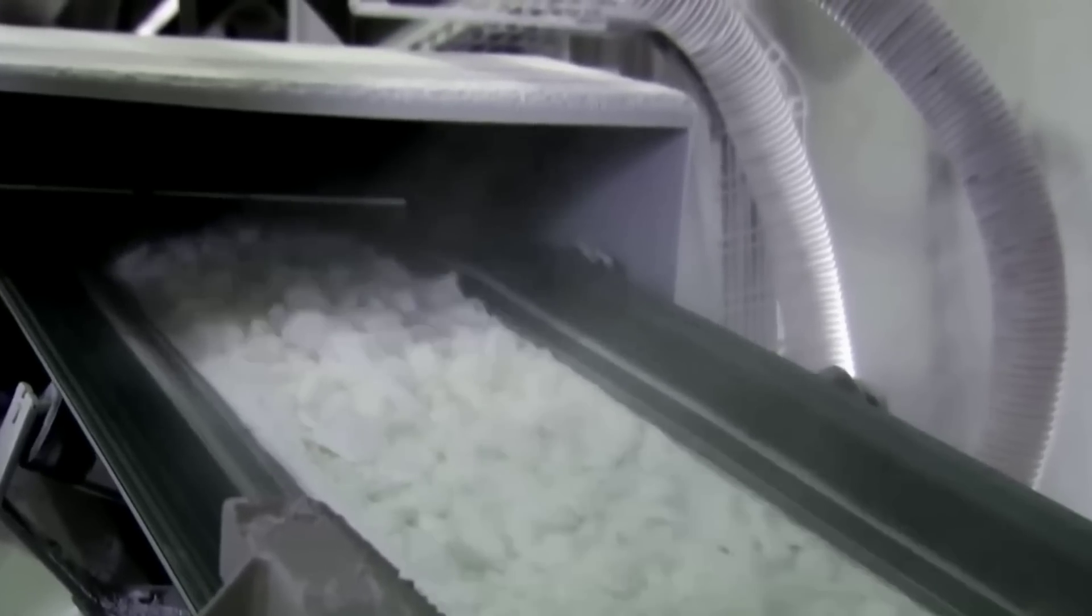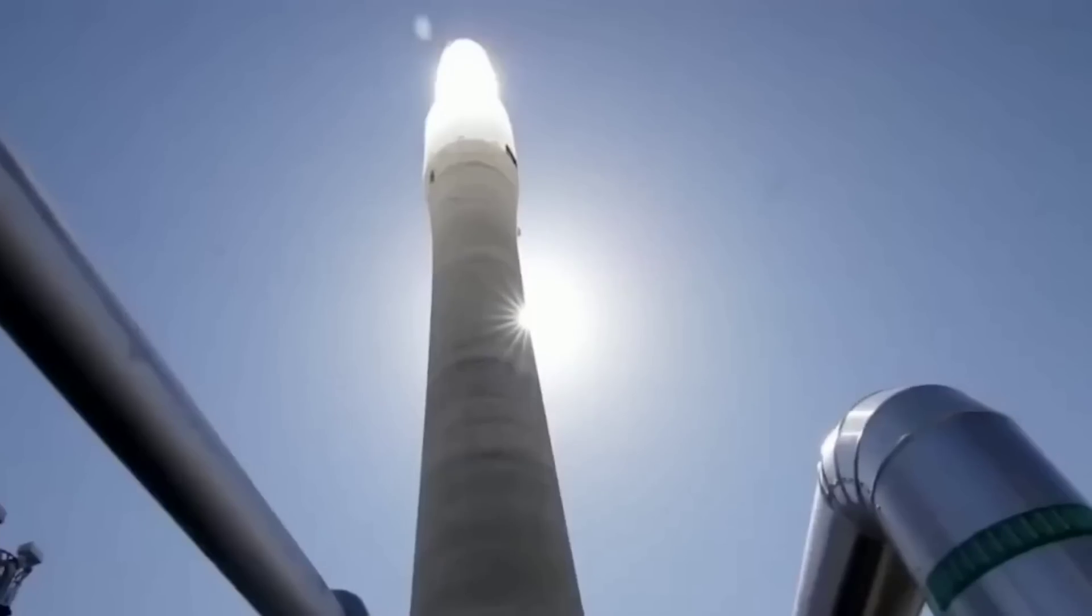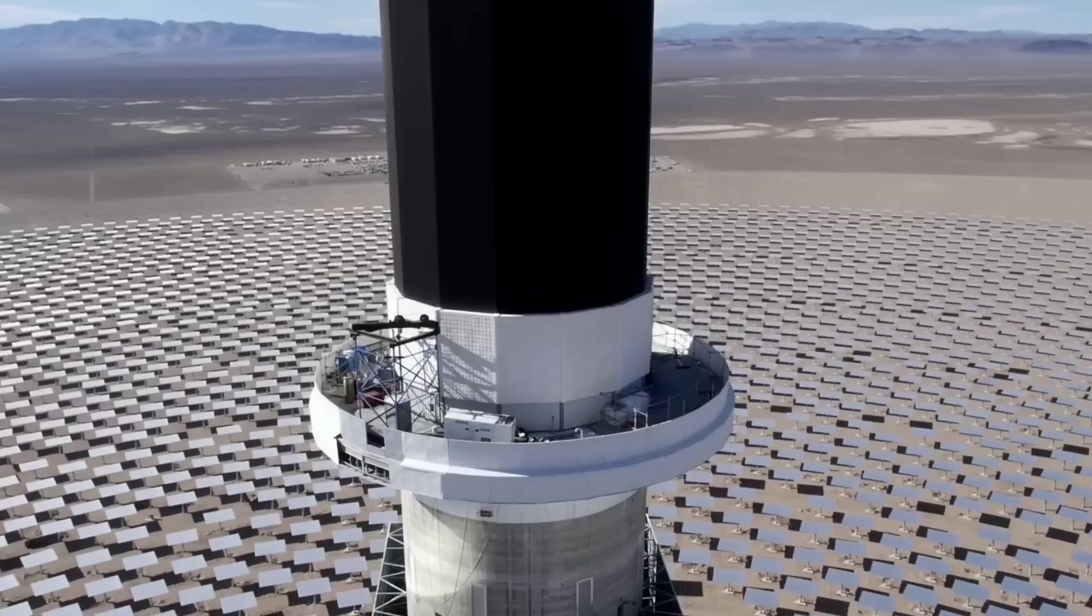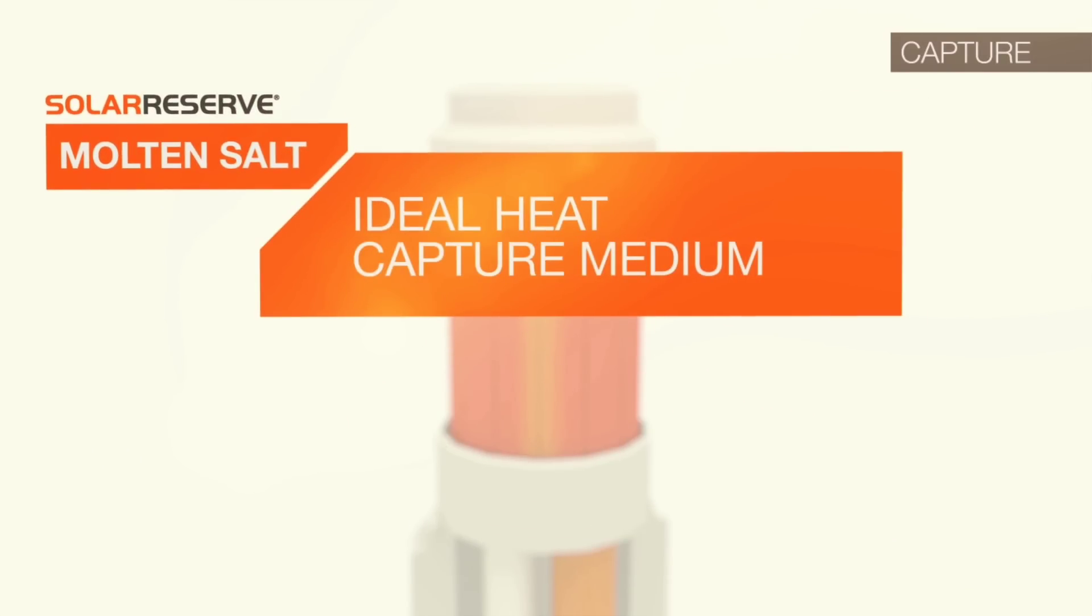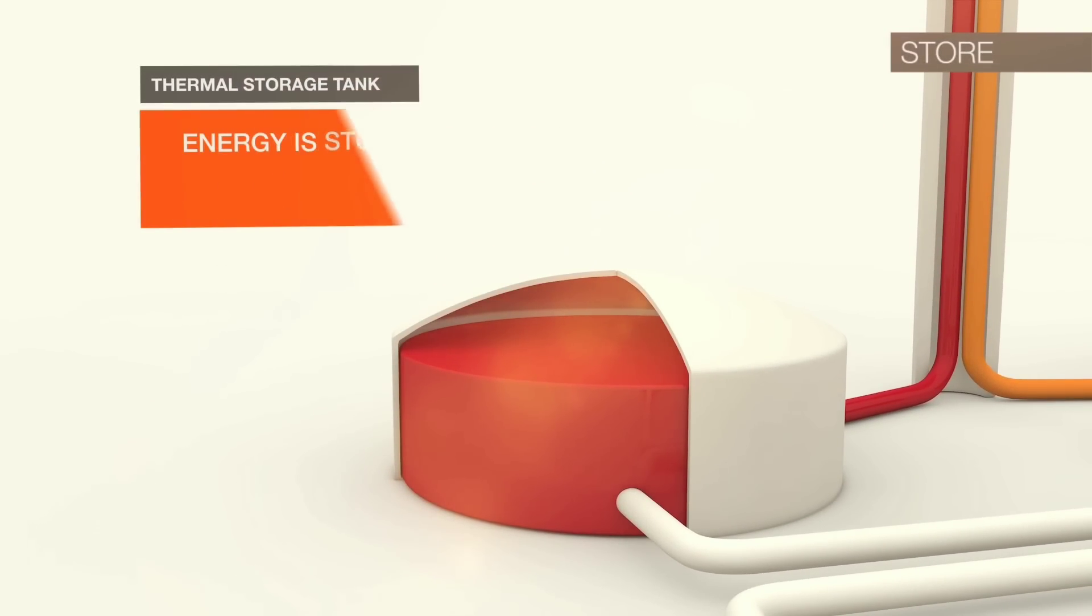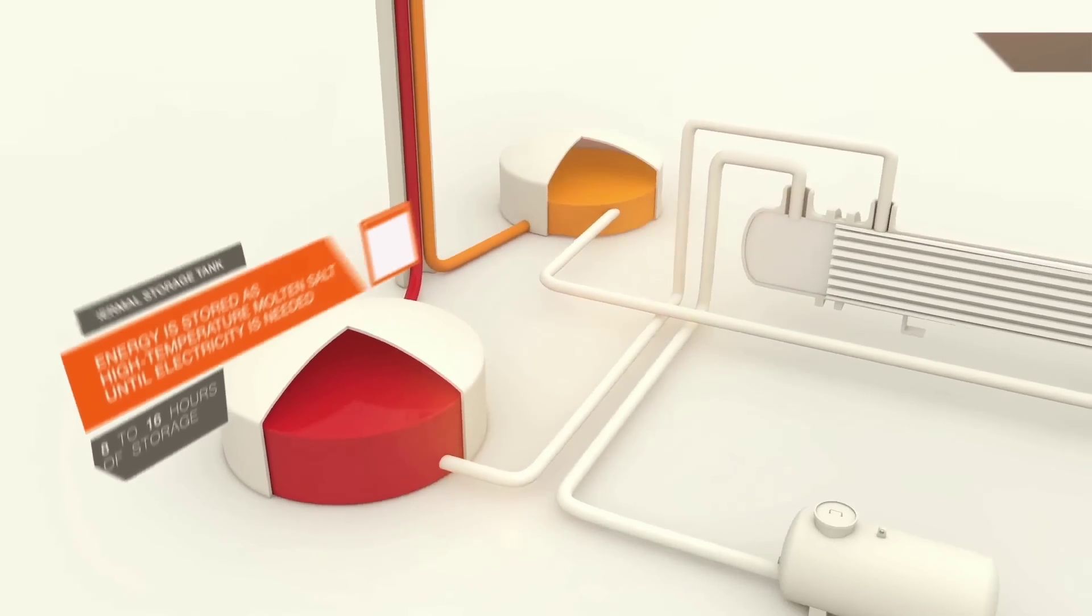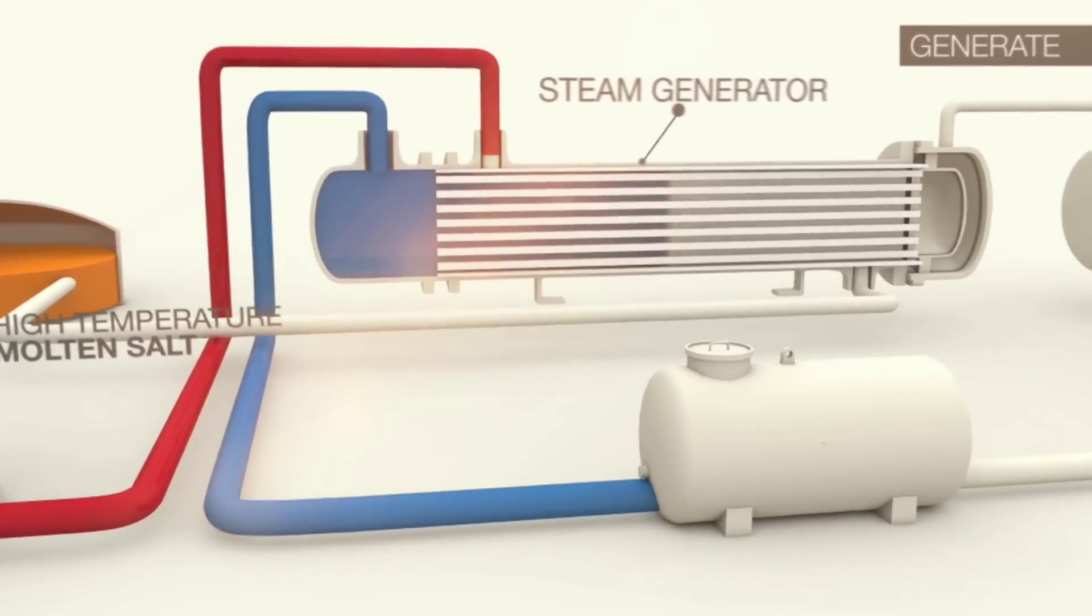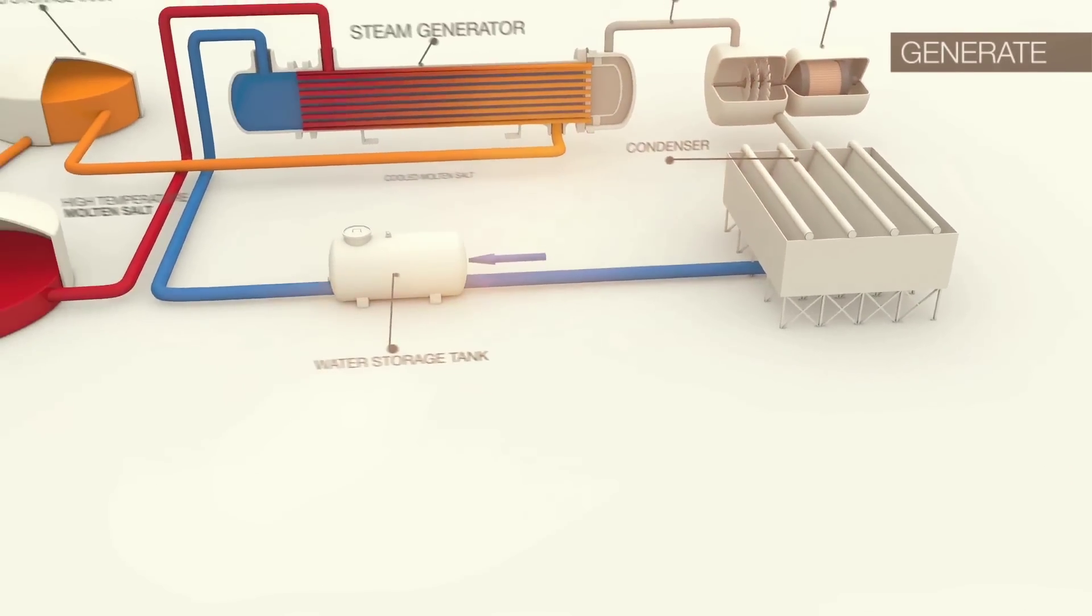The project consisted of 10,347 heliostats, which are large mirrors that track the sun and reflect its rays onto a central tower. The tower was about 656 feet tall and had a receiver at the top, where molten salt flowed through pipes and got heated by the sun's thermal energy. The molten salt reached temperatures of up to 1,050 degrees Fahrenheit and was stored in a large tank. The hot salt was then pumped to a steam generator, where it heated water and created steam that drove a turbine to produce electricity. The cooled salt was then returned to the receiver to be heated again.